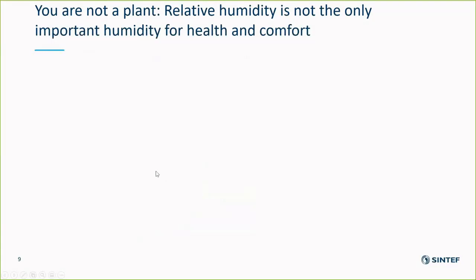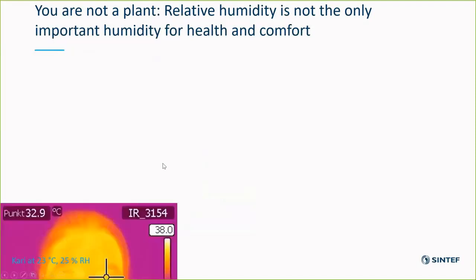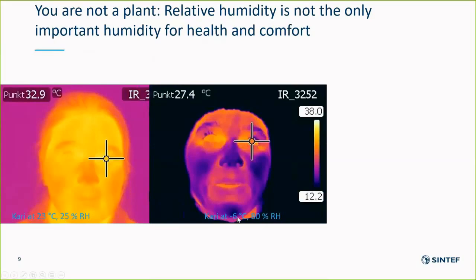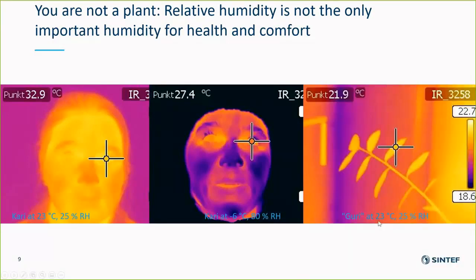Remember that most of you are not plants, so relative humidity is not the only important humidity parameter for health and comfort. Your eyes — for instance my colleague Kari's eye — will be subject to evaporation in an office environment at 25 percent relative humidity. But the same will happen if she goes outdoors at 80 percent relative humidity and minus six degrees. So it's the pressure difference that drives evaporation, and absolute humidity or partial pressure of water vapor would be a better way to assess that than relative humidity.